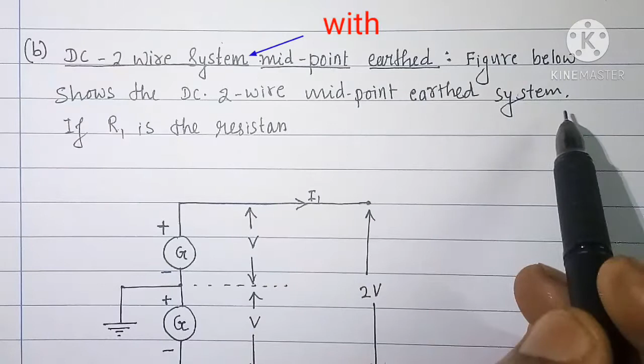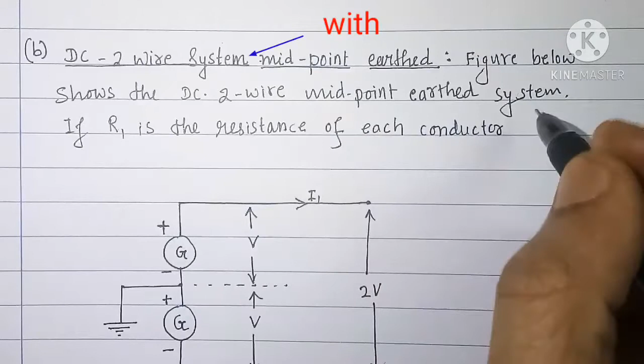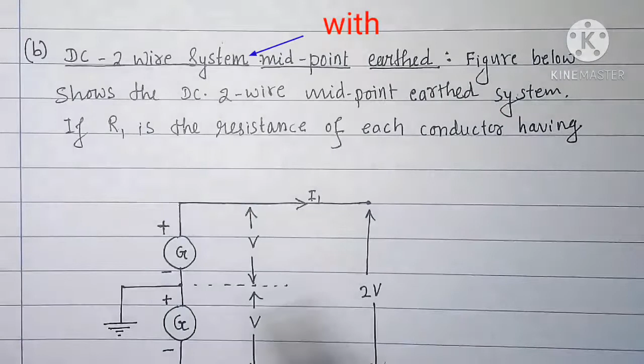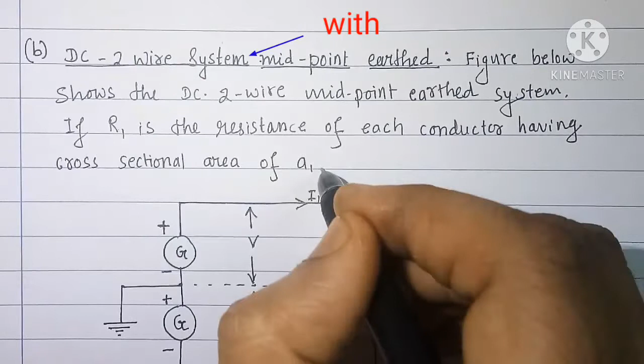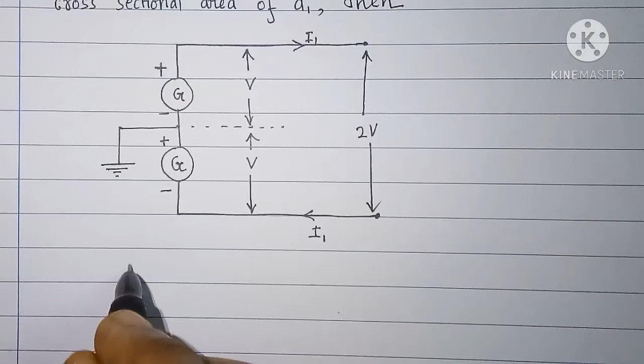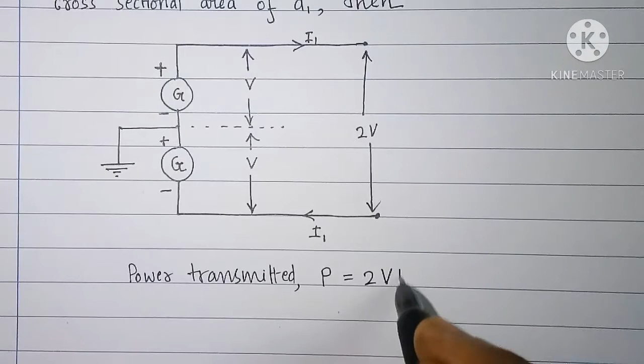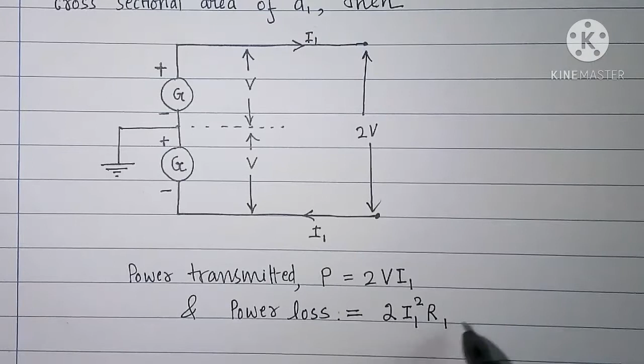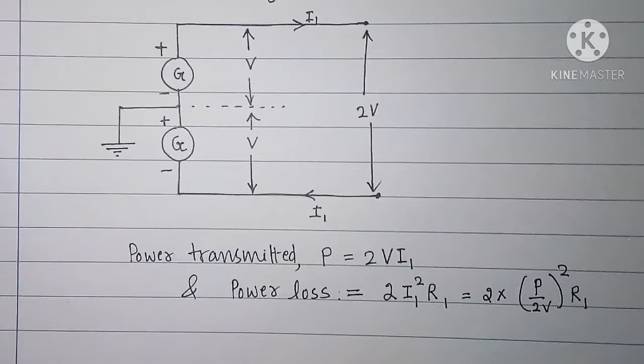Figure below shows the DC 2-wire midpoint earthed system. If R1 is the resistance of each conductor having cross sectional area of A1, then power transmitted P is equal to 2 into V into I1, and power loss is equal to 2 times I1 square into R1, that is equal to 2 times P by 2V square times R1. It simplifies to P square upon 2V square into R1.